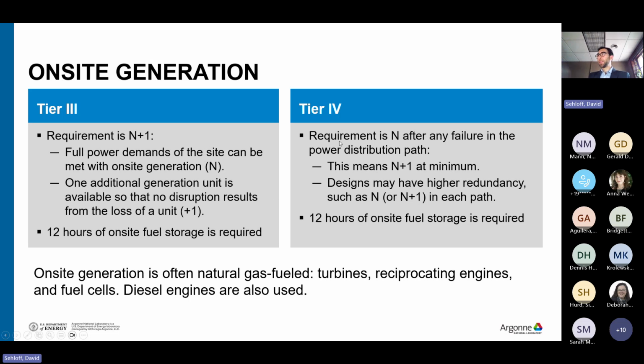Tier 4 is stricter. The requirement is that after any failure, there is N, so the full power demands of the facility can be met. So that's at least N+1, but often you'll see N in each path, so that would be 2N or 2N+1, where you have N+1 in each path. And again, 12 hours of on-site fuel storage. This fuel is often natural gas, but it may be diesel as well. There are a lot of options for this on-site generation.